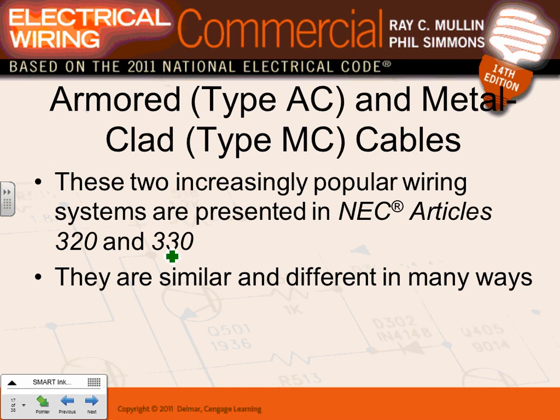MC and AC cable: if you're an engineer, you're going to be looking at MC cable. The difference is that MC cable has an insulated grounding conductor - that's the key difference. They look alike, except MC cable is more robust with an equipment ground conductor inside it.